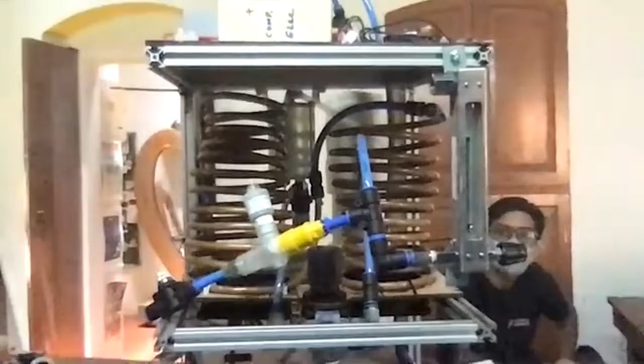Around the oxygen sensor, what is the flow rate? 100 ml. Yeah, 100 ml per minute or something. So very little coming out of here. So that's all you're adjusting because this is an open system. All the air is actually going through this into this. So only very little air is going through this. So this is the right way of measuring it according to all the documentation that we read. That very low air flow needs to go into your oxygen sensor.